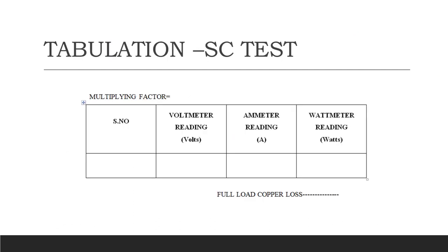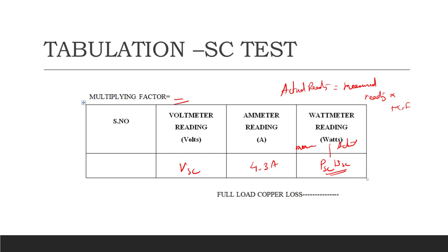This is the tabulation for the short circuit test. Set the rated current of 4.3 amps, then find VSC (short circuit voltage) and WSC (short circuit power). The actual reading is the measured reading multiplied by the multiplication factor. Whatever you get as the actual reading will be the full load copper losses. From the copper loss WCU and core loss WC, we are going to find out the efficiency and regulation.